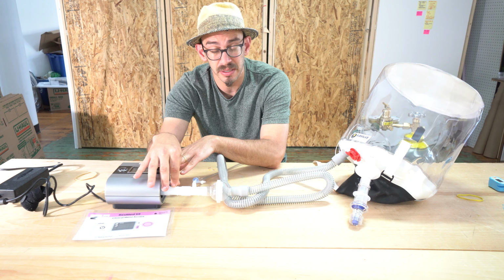Specifically, one of the cases that you do not want to happen is if your patient starts to drop their oxygen saturation, you crank up flow, and then you very quickly see the CPAP turn off and you lose PEEP. That's obviously not a good situation. This circuit allows air a pathway to come out, and so your CPAP will not go into a tube blocked state as long as you have this circuit in here. That's why that's important.